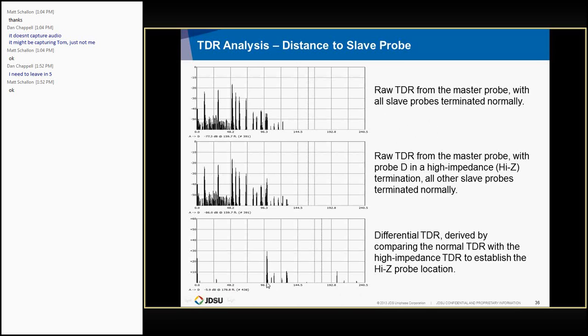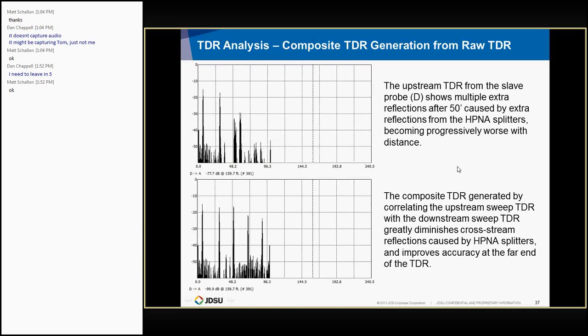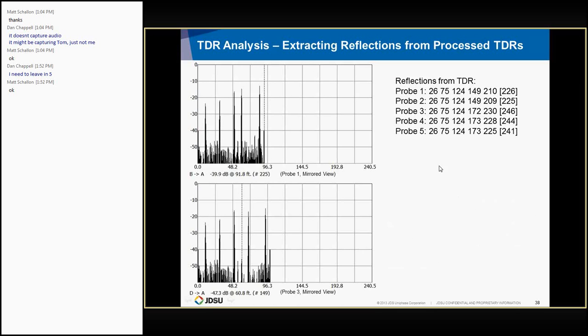This is the actual graph of the composite, the differential TDR, and it picks out with good accuracy the point at which the distance to that probe. Then the composite TDR is generated. This is D to A looking upstream. And down here in particular, you've got a lot of extra reflections that would show up in the original approach as a lot of rat-a-tat-tat reflections down at the end by the master probe. And you've got extra reflections up here. But when you do the composite, then you get clean stuff here in the middle, and this picks it out pretty accurately. And then you take the mirrored image.